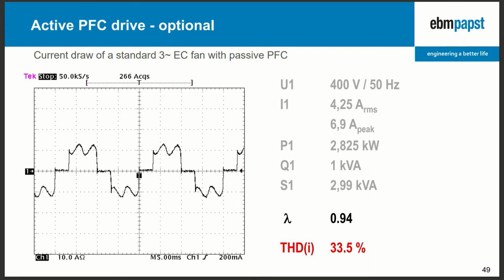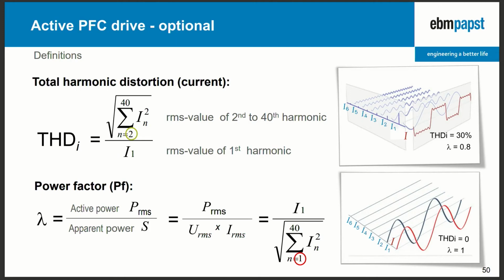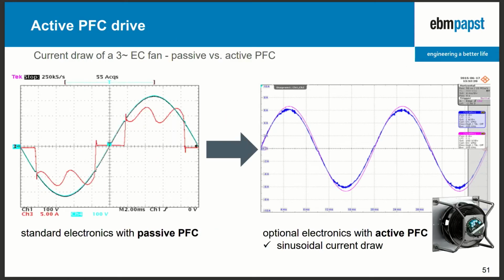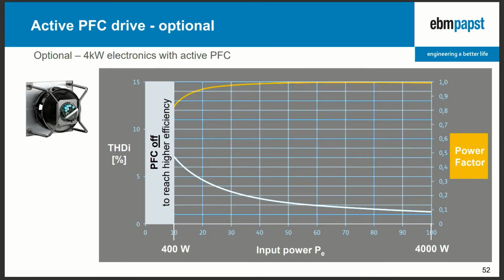In some installations, it's required to be below 5%, and to do that, you can use filters. We have created an electronic where this filter is integrated. This electronic has a power of 4 kilowatt. What we do here is we bring the current in line with the voltage, and we also bring it to a sinusoidal wave, not like this one, which is quite uneven. If we do that, we are below the required 5% of THDI value.